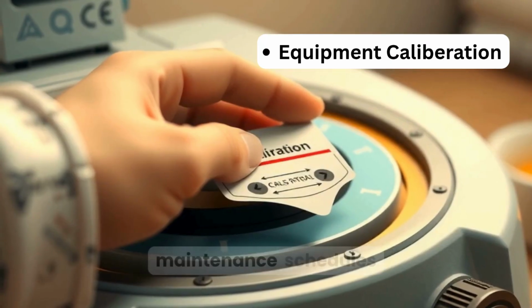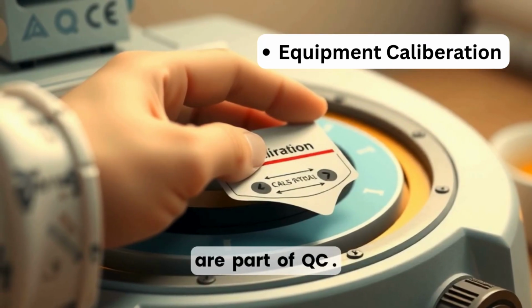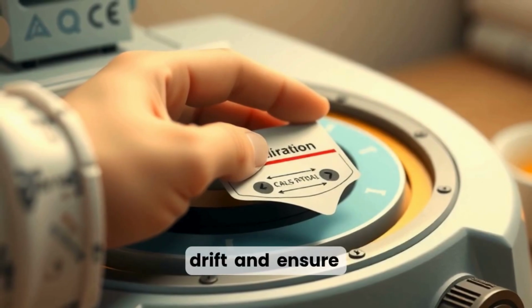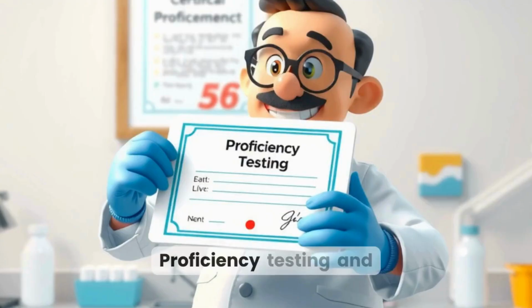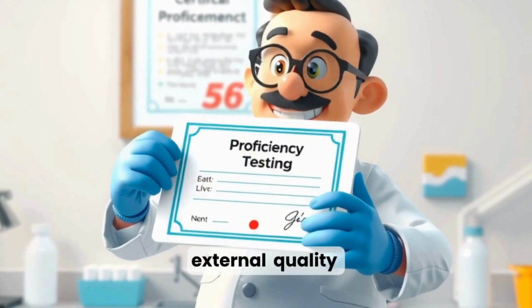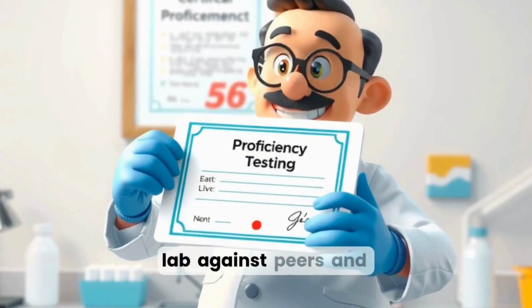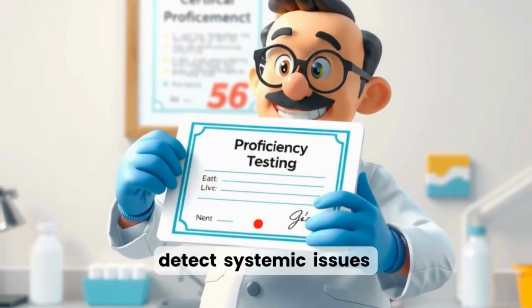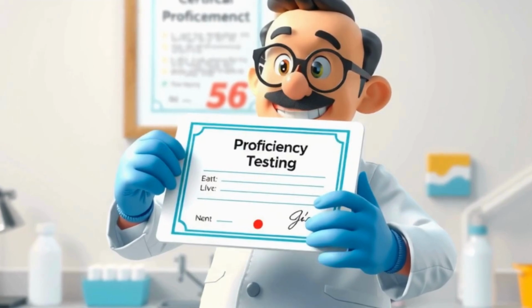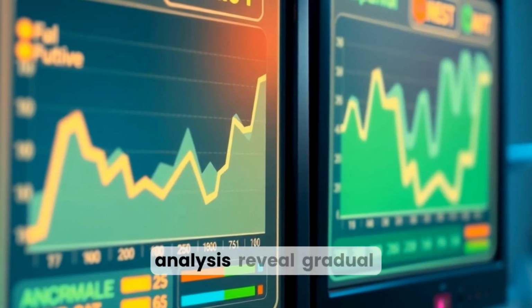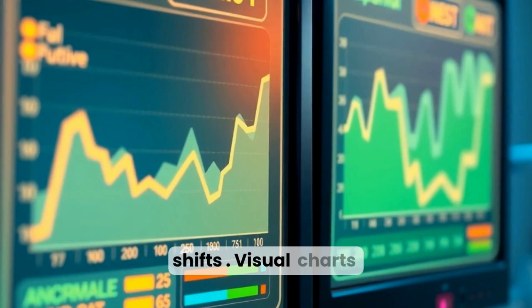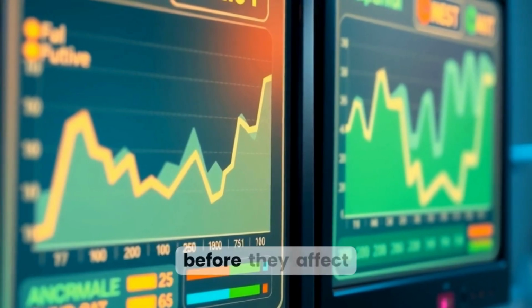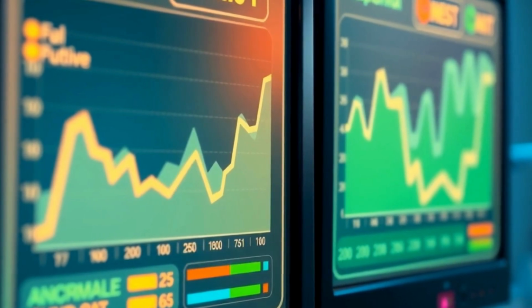Equipment calibration and maintenance schedules are part of QC. Regular checks prevent drift and ensure consistent performance. Proficiency testing and external quality assessments benchmark a lab against peers and detect systemic issues beyond daily QC. QC charts and trend analysis reveal gradual shifts. Visual charts help teams spot patterns before they affect patient results.